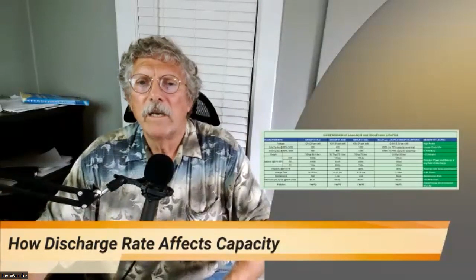And it's important to note that batteries have different amounts of capacity depending on how quickly they're being discharged. So when you're designing your system, let's say you put in a relatively small battery, but you're going to use it pretty quickly, and you've been told it has this amount of capacity - it may not have that amount of capacity, because you may be discharging it too quickly. I think this diagram talks a little bit about that.